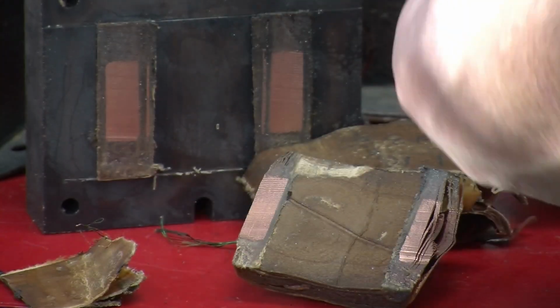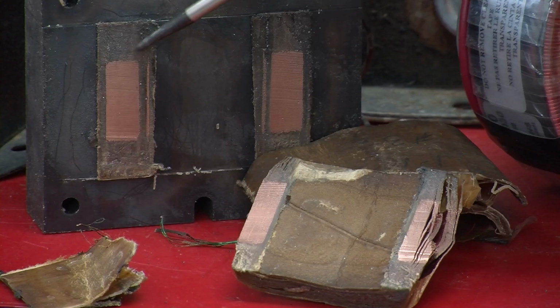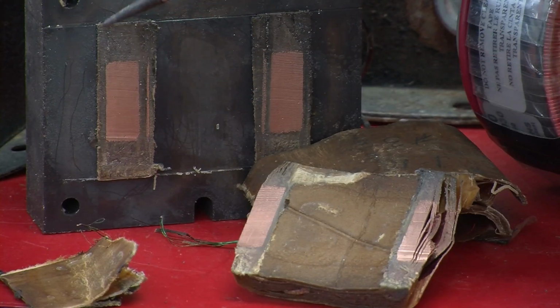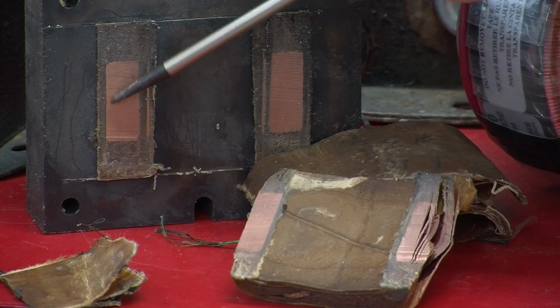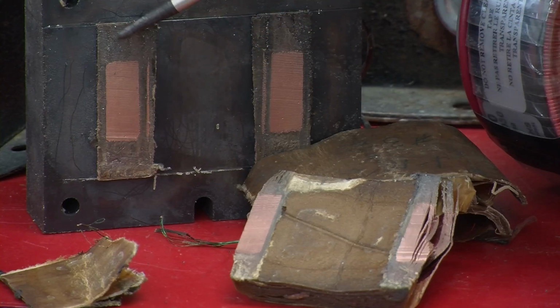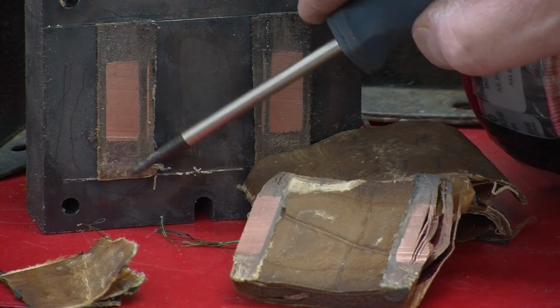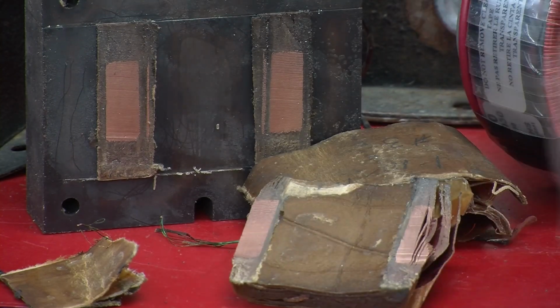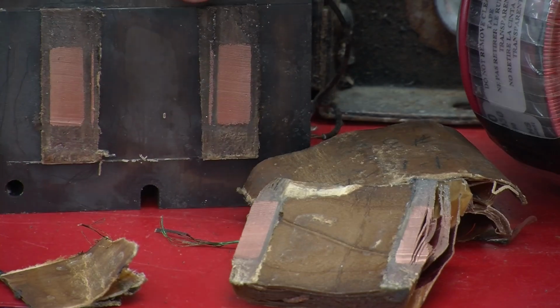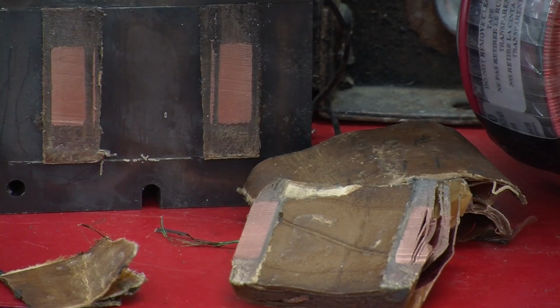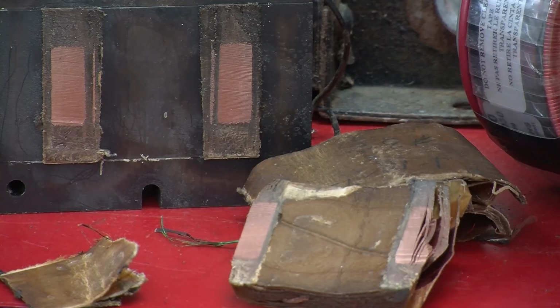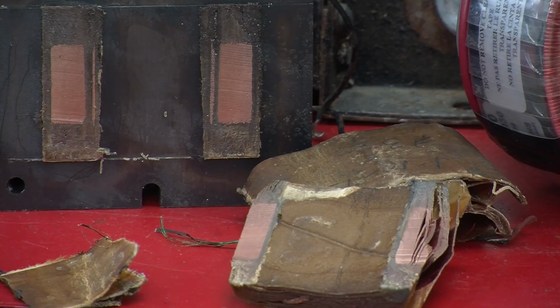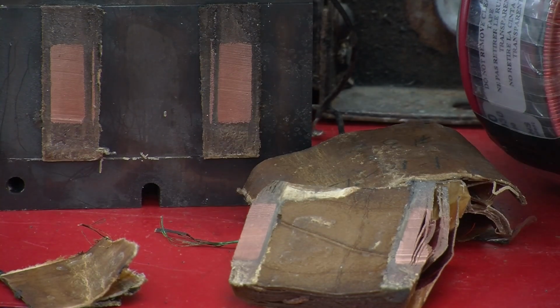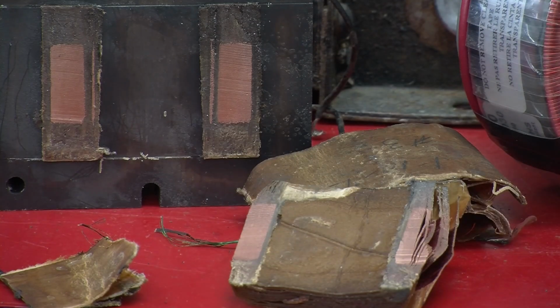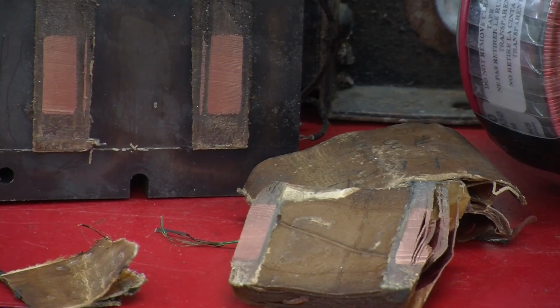One other thing worth pointing out on this transformer is you'll notice there are big areas here and here with no windings. Normally this would all be filled, and I think it's because this is a very high voltage winding. I believe it was in the 5 or more kilovolt range. So what they've done is they've put insulation in here. So this core is probably way bigger than it would normally need to be for a transformer of whatever power it was designed for, because they had to devote so much space for insulation. So that's another compromise. Anyway, there you have it. Those are some of the compromises that transformer designers need to consider when coming up with all the wonderful transformers that we use in our electrical lives.